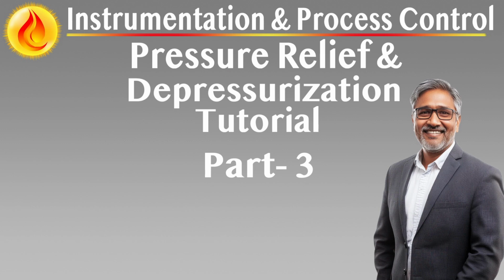Limit the pressure drop in inlet piping to 3% or less of the relief valve set pressure to prevent valve instability. For liquid service, additional care is required due to the incompressible nature of liquids. Pressure drop during flow acceleration can quickly exceed tolerances.